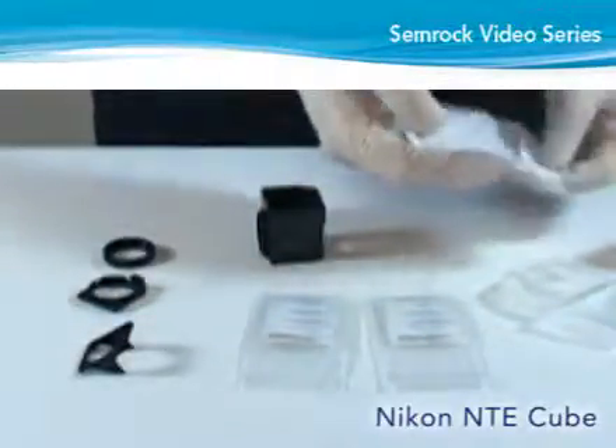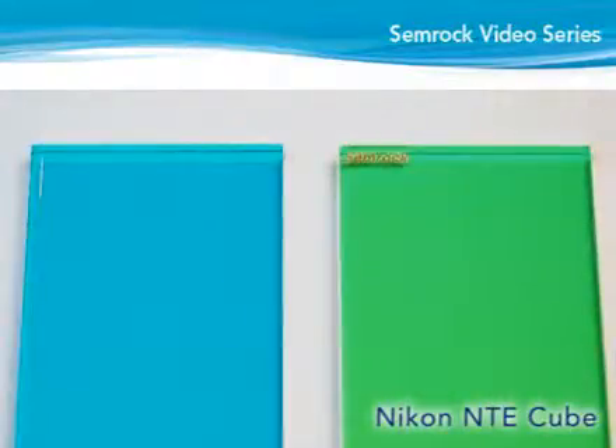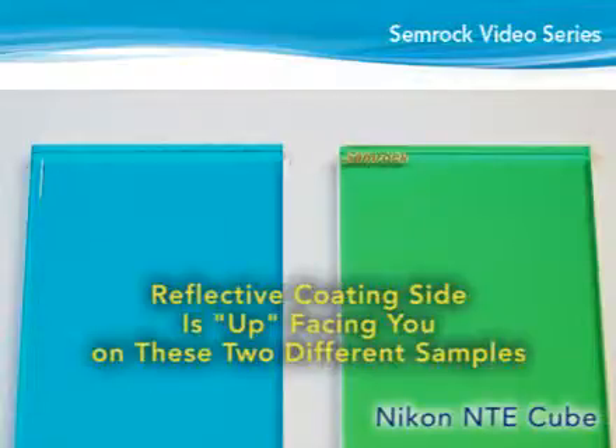Next, determine the reflective or coated side of the dichroic for proper orientation in the cube. If the dichroic has a small linear mark or inscription in one or both corners, the reflective coating side is facing you when the long side of the dichroic is vertical and the mark is in the lower right or upper left corner. If the dichroic does not have any marks, lay the filter flat on a clean white surface and look at the far edge of the glass.